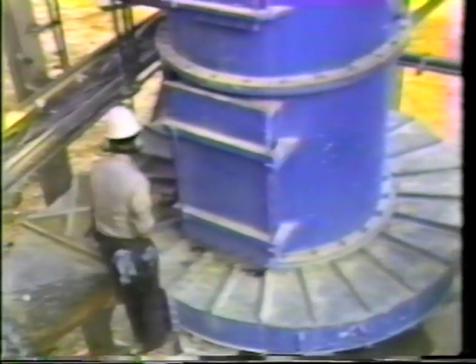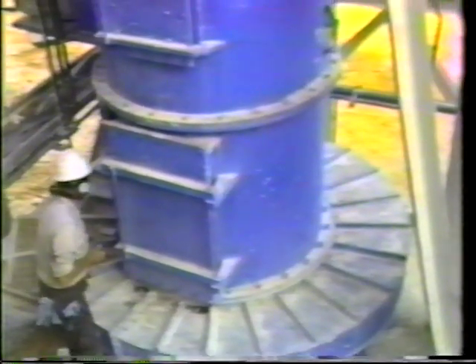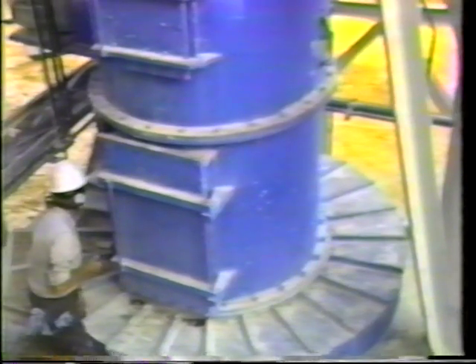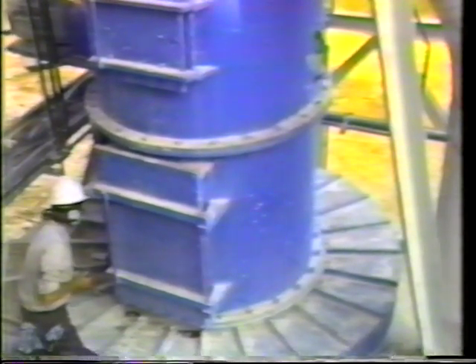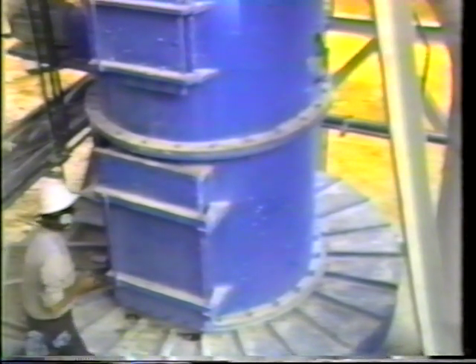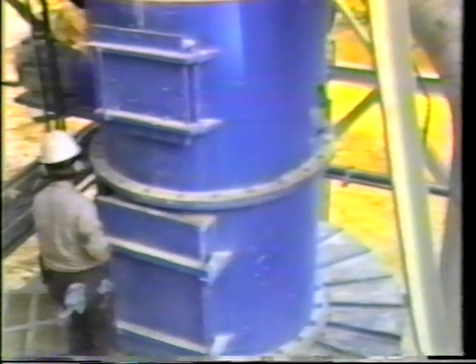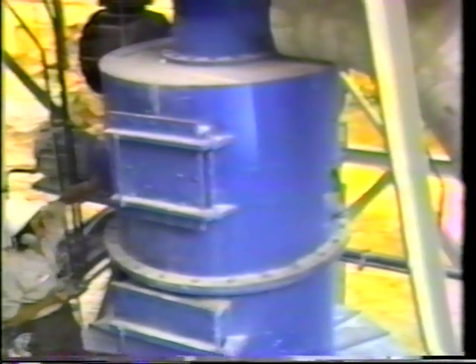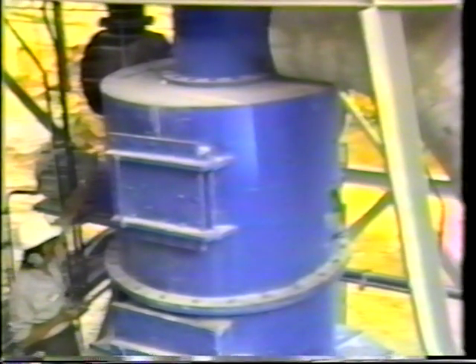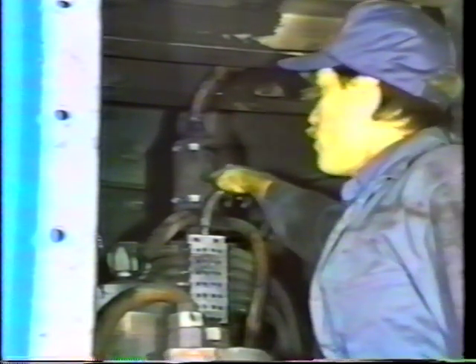As the air comes into our wind box, it circulates around and comes through what is known to us as porthole liners, or porthole openings in the bottom of the mill. The air enters, it rises, bringing the material with it. The lighter material passes through our classifier and out through the top. Comes out of the union behind this flexible hose.